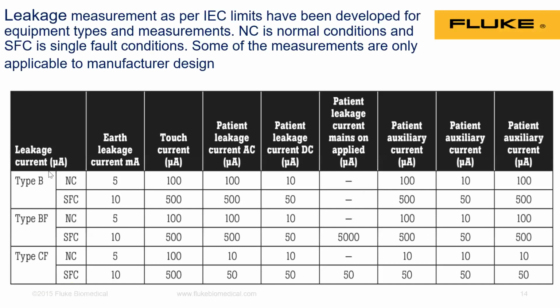As I was saying, IEC has given the guidelines. A few slides back I showed the types of medical device: type 1, type 2, and further type B, type BF, type CF. So what are NC and SFC? Like Mr. Gopakumar was saying, one is the normal condition and the other is the single fault condition. Normal condition is the actual condition when the medical device operates. What the earth leakage current, touch current and patient leakage current should be is specifically given.